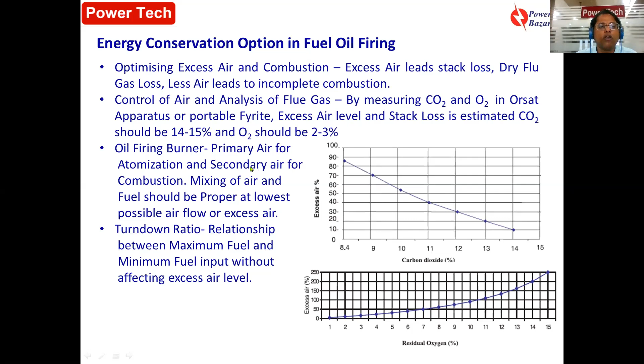So three things are important. You have to optimize your excess air and combustion. You have to control and analyze the flue gas. If oxygen is very high, then you have to take some action. You have to reduce excess air. If CO2 is very low, that again is not a good sign. You have to restrict excess air. But while restricting excess air, you should also ensure that the fuel is completely burnt. And another one is the oil burner. By controlling the primary air and secondary air flow, you can also optimize the firing of the burner, by which you can control your fuel firing.